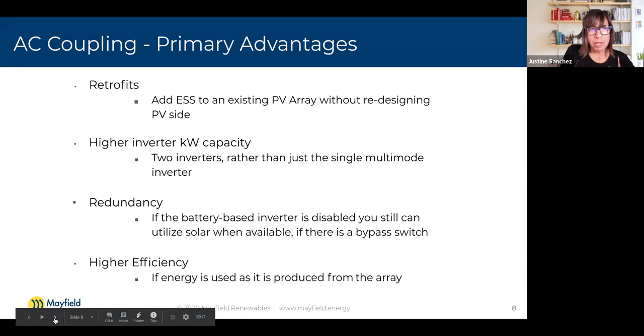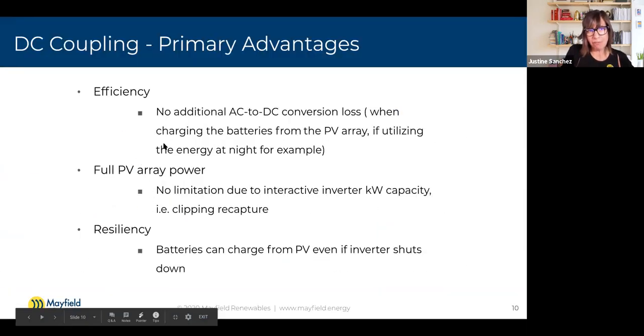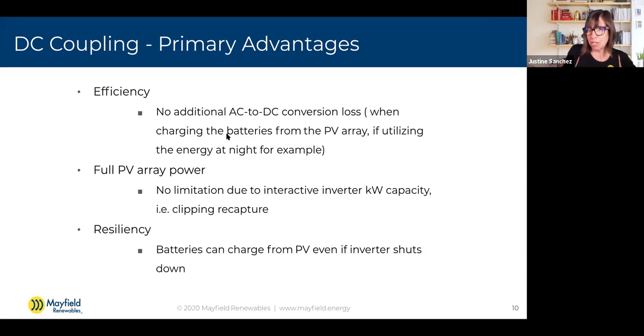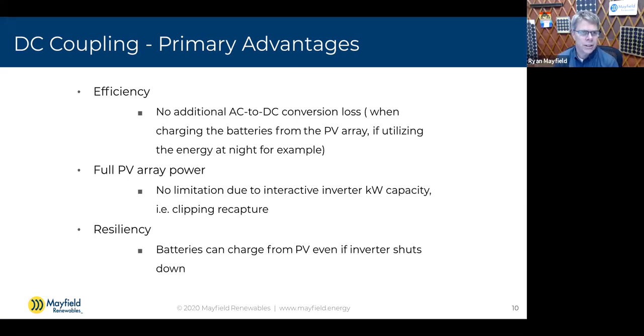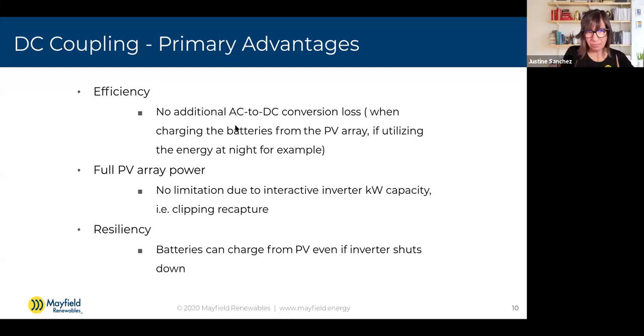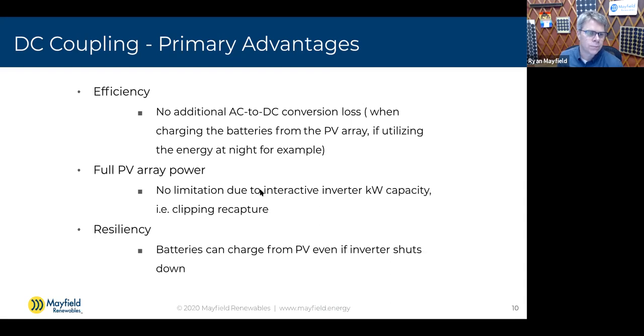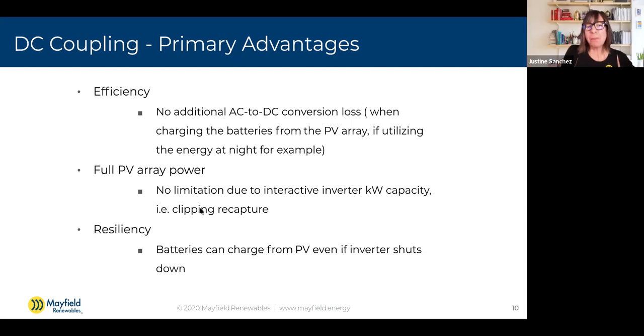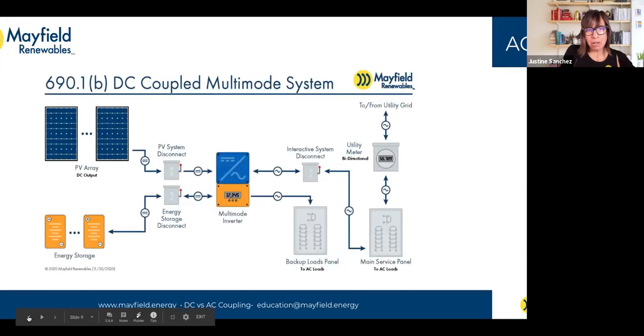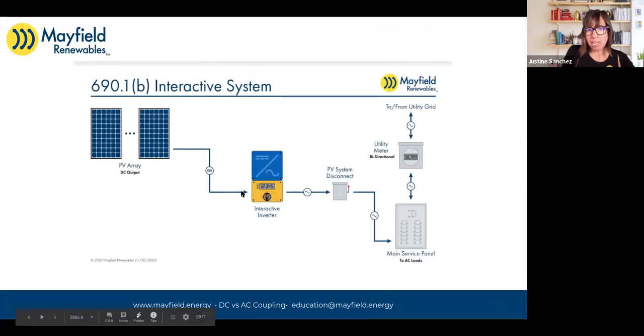So if I jump to my DC coupled advantages, I have efficiency as one of the advantages of a DC coupled system. And that's with the assumption that you're having to convert DC to AC, AC to DC, and DC to AC again. So more efficient when you're using it to charge the batteries directly. Exactly. When you're considering that portion of the use. Mm-hmm. Right. Yeah. So the big one that I really want to get to today is the full PV array power. Okay, so I'm going to go all the way back to our initial diagram here, our interactive system.